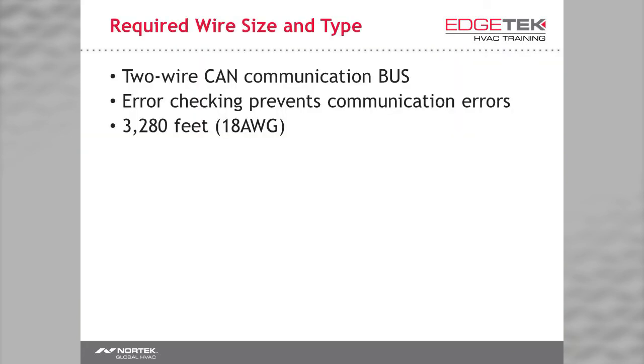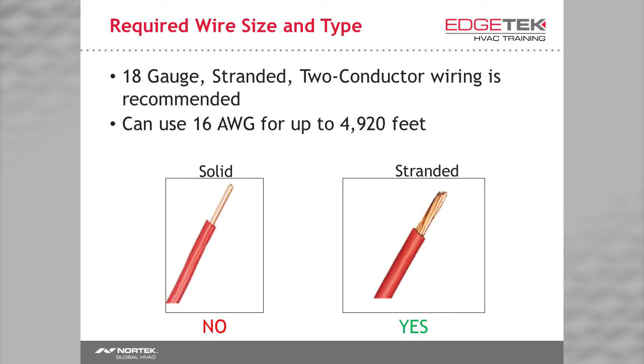Our communication is set up using a 2-wire CAN bus, with its main advantage being that it constantly checks for communication errors. In other words, you can lose one indoor unit and the system will continue to operate, unlike pretty much every one of our competitors. Using 18-gauge wire, you can run up to 3,280 feet of wire. Should be enough. You'll be using 18-gauge stranded 2-conductor wiring.